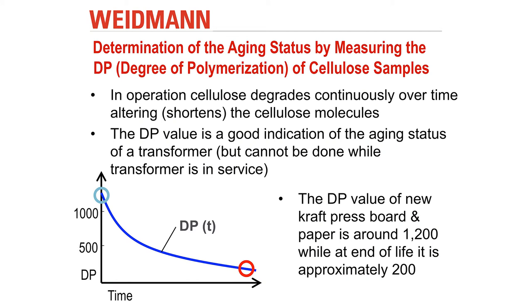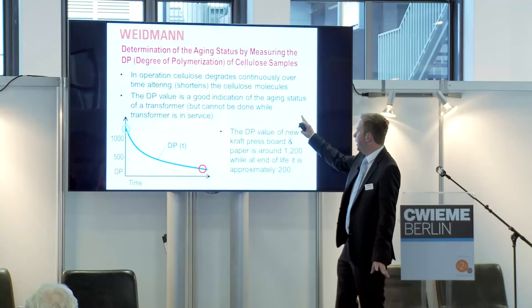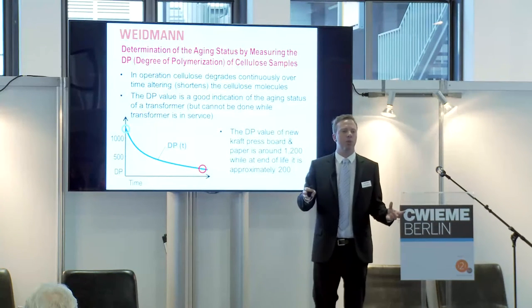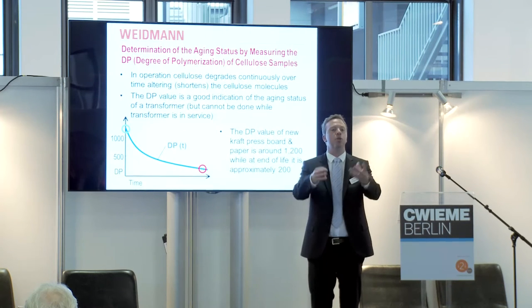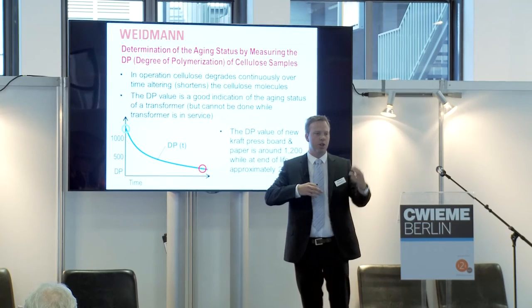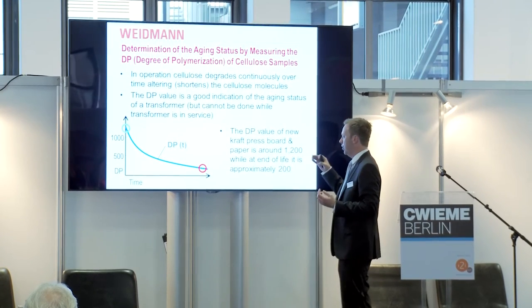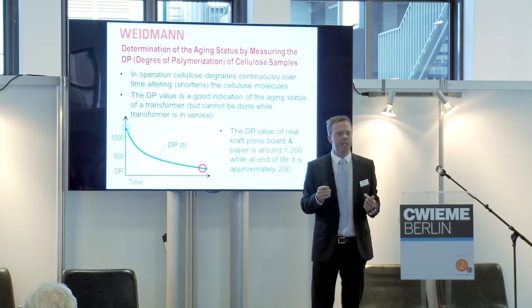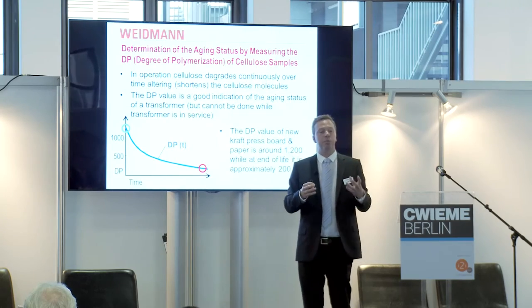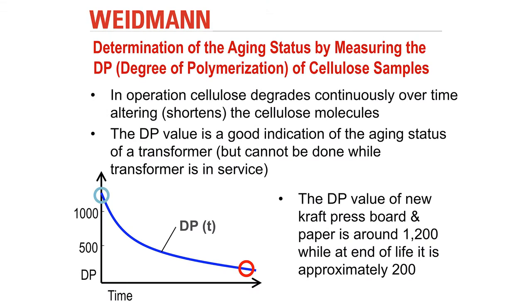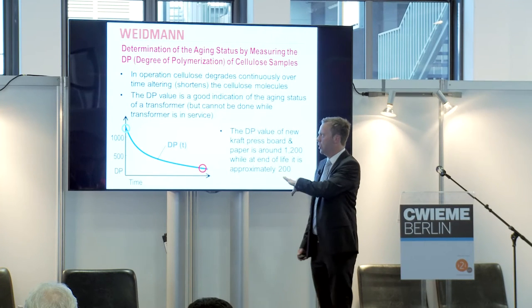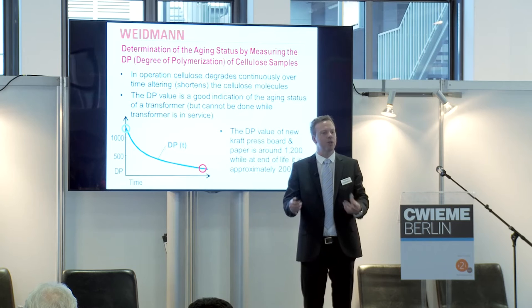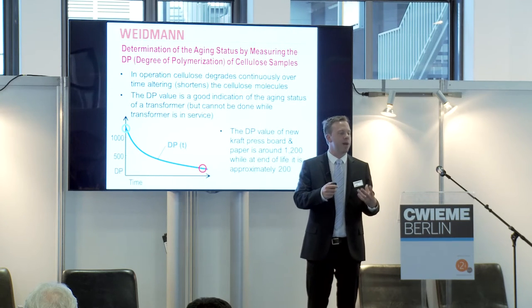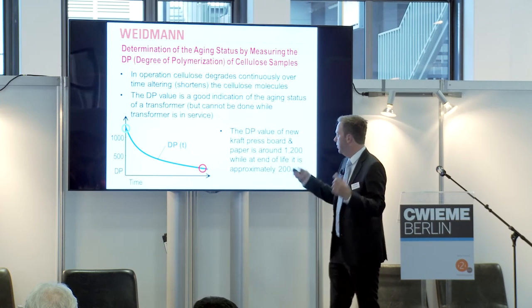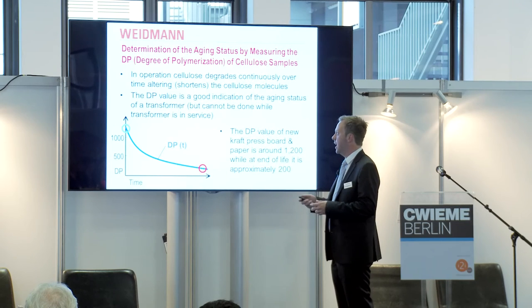So onto this subject of aging status, looking at DP. The DP value of a new transformer is 1200. As we ship a transformer from a manufacturer, as Weidmann ships transformer insulation, the DP is somewhere around 1200. At the end of its life, it's around 200. This is a perfect way to measure the breakdown of insulation through the life of the transformer. However, you can't do this on a live transformer in the field. The reason we know these numbers is because people have looked at retired transformers, broken them down, and measured the DP content. So this is a direct measure of the breakdown of the insulation.